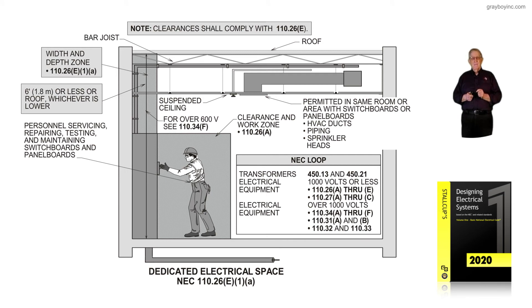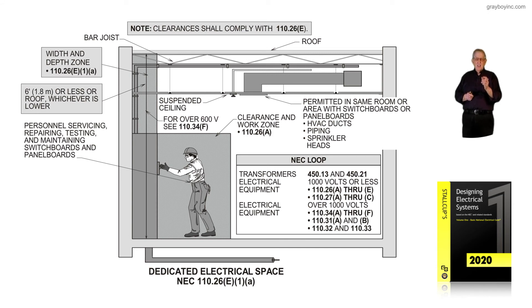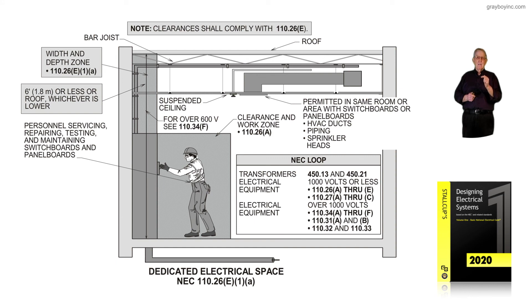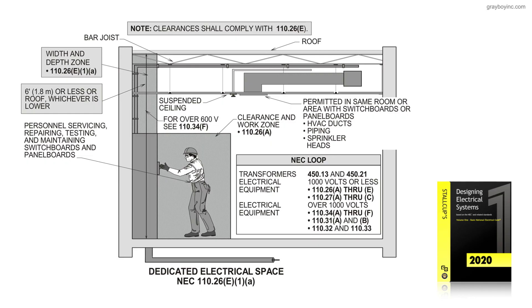Figure 5-10.1A simply deals with the dedicated electrical space above the equipment, but we also have space in front of the equipment. The gray-scaled information shows the six-foot above the equipment, the three-foot depth, and the width of the equipment. The six-and-a-half-foot headroom is based upon the height of the equipment because the equipment has a greater height than the electrician. That's what this figure is illustrating — the dedicated workspace in compliance with NEC 110.26E1A.